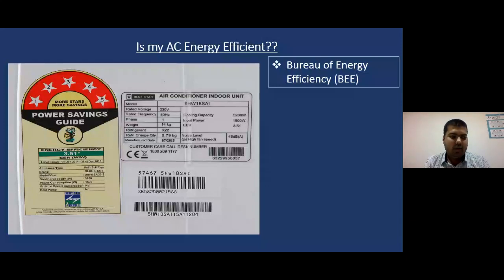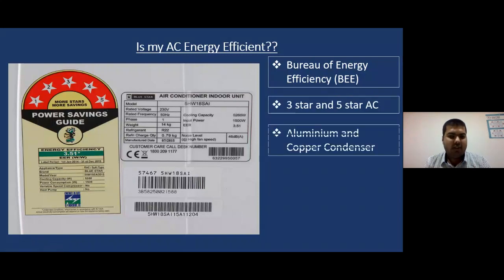And again, one more thing, for variable speed compressor, it is mentioned as no. So it is a fixed speed compressor machine. It is not an inverter or a variable speed machine. That means if my temperature goes to 24 degrees Celsius and it has achieved the desired temperature, my compressor would cut off. It would start again only when the temperature rises. There would be many on-off cycles of the compressor.